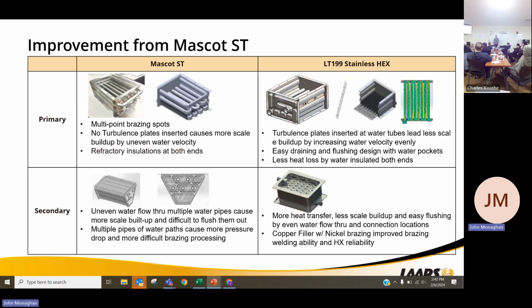The Mascot ST was out for a while. Different style heat exchanger. There's no U-bends in there. Cuts down on the turbulence and the pressure drop through the heat exchanger. And the secondary heat exchanger was kind of like an inverted A coil, which cut down on the flow and the airflow through it. So we've improved all of that.